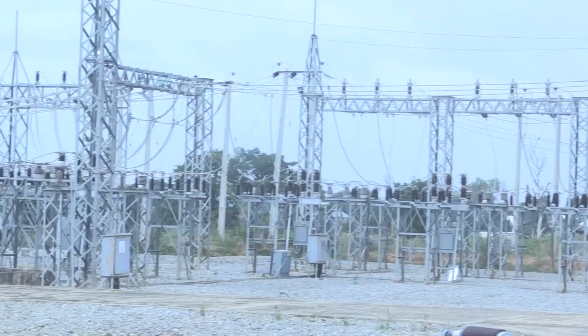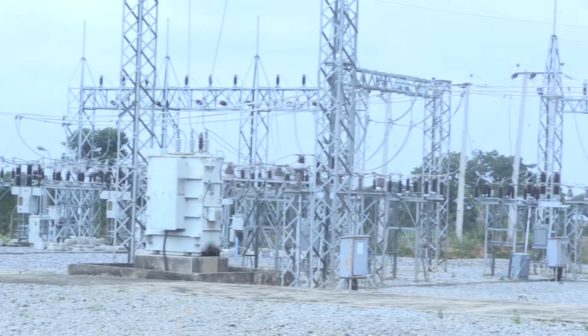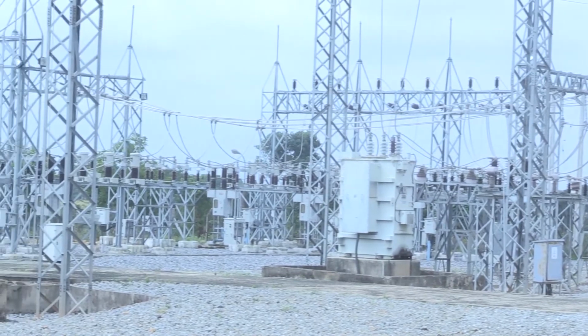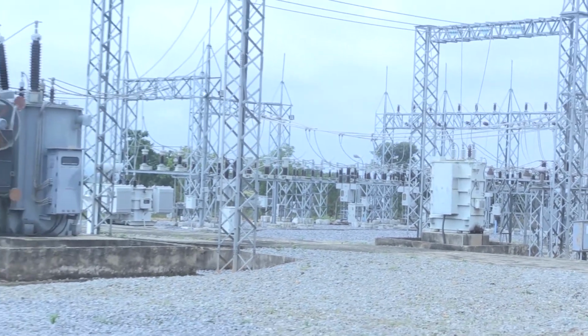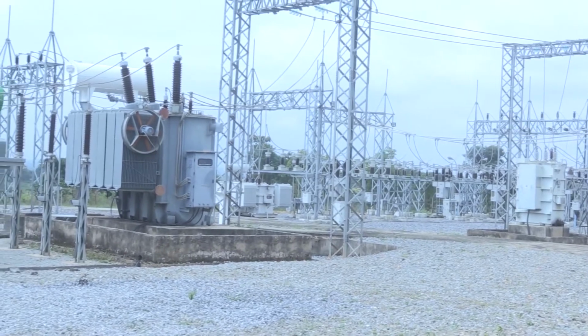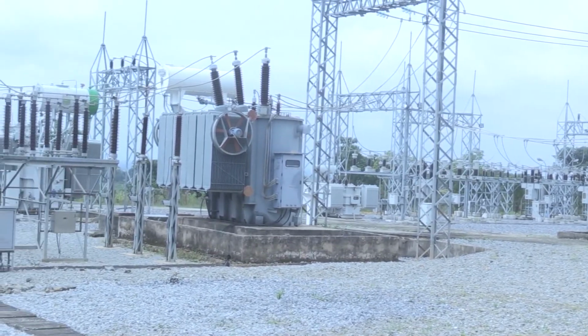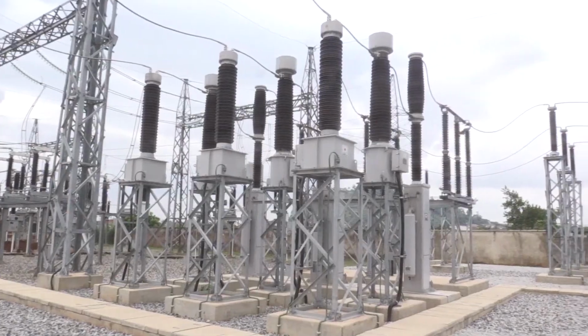The capacitor bank is to improve the voltage at whatever level we are going to install it. In our own case here, we have it installed at the 132 kV side, that is at the 132 kV bus. On the 132 kV bus here, what we normally get from Katampe and Gwagwalada, which are our sources of supply to this place, we do get at times 124 kV. So when you install the capacitor bank, you tend to boost the voltage up. There's an improvement in the voltage here, so the issue of having low voltage from our own end is eliminated.